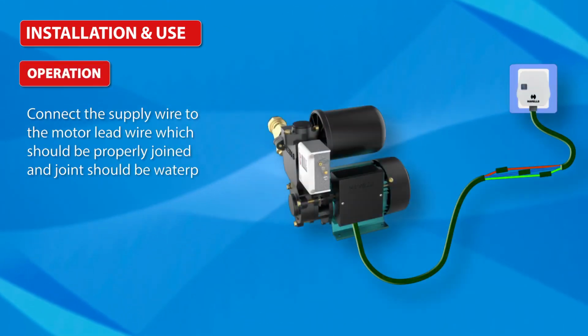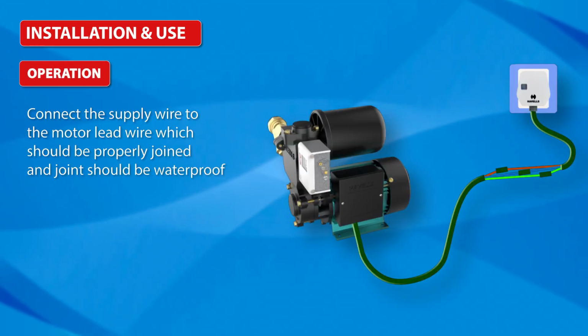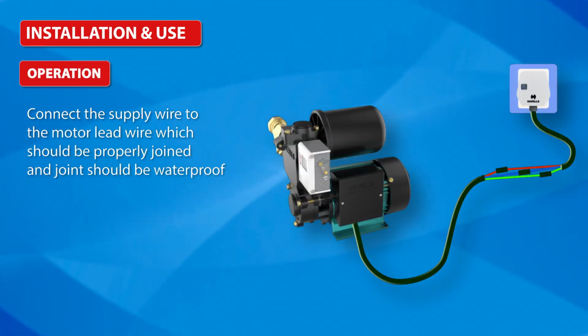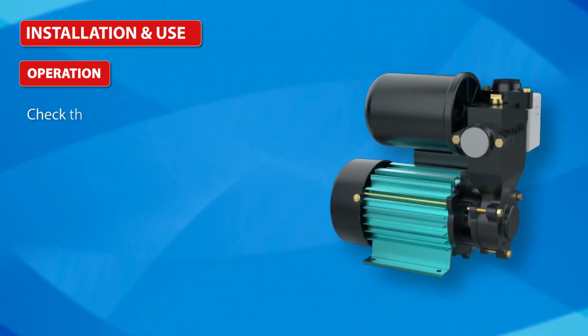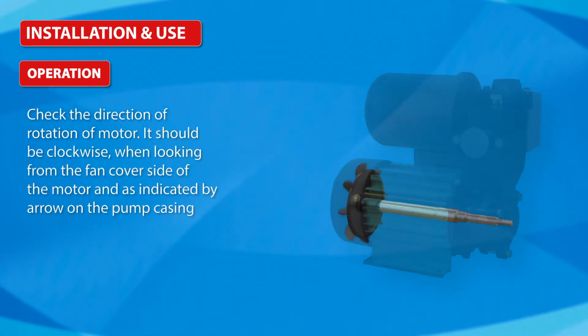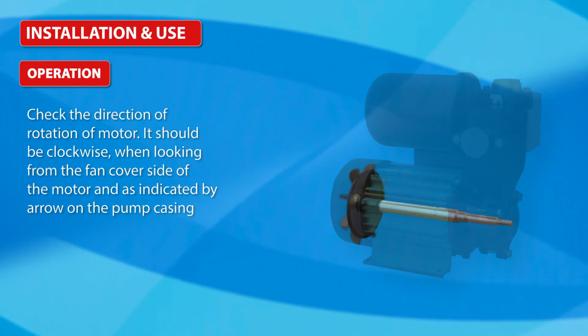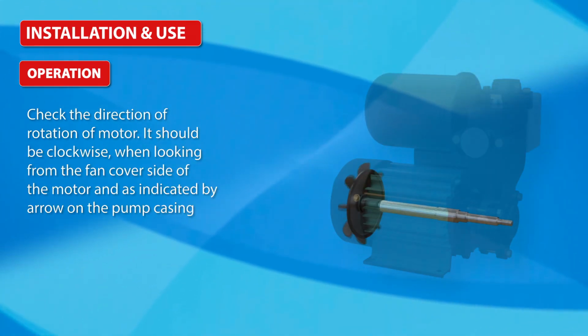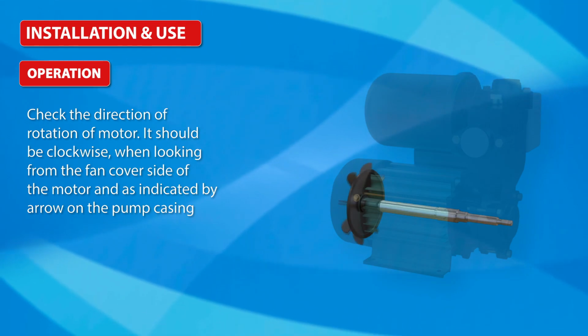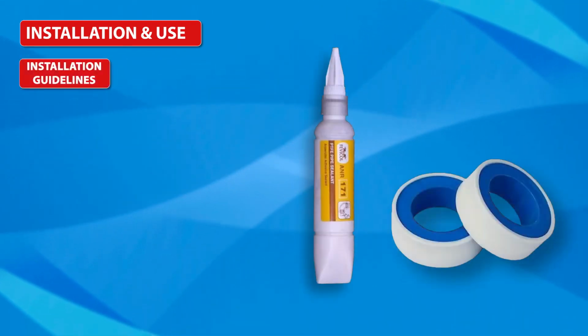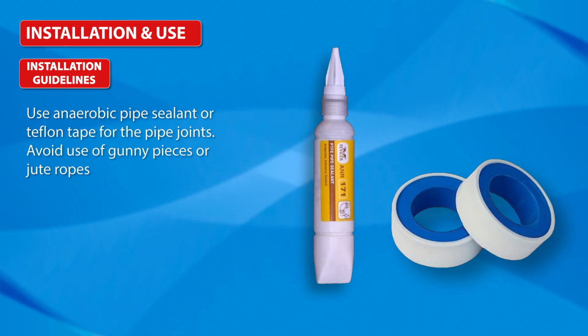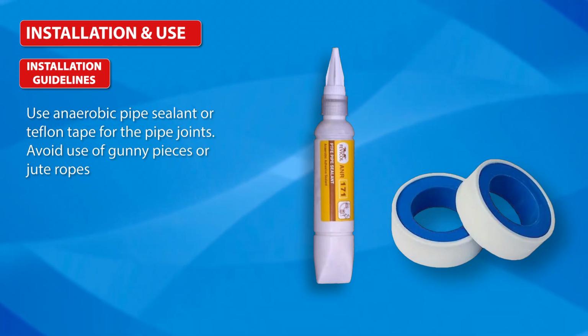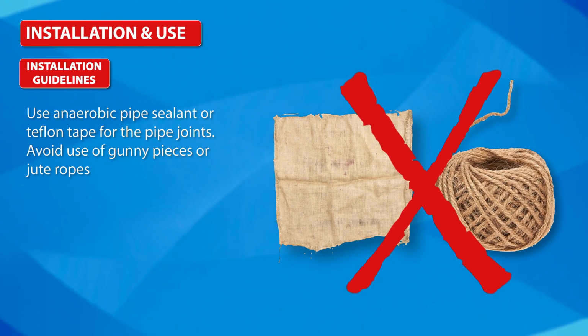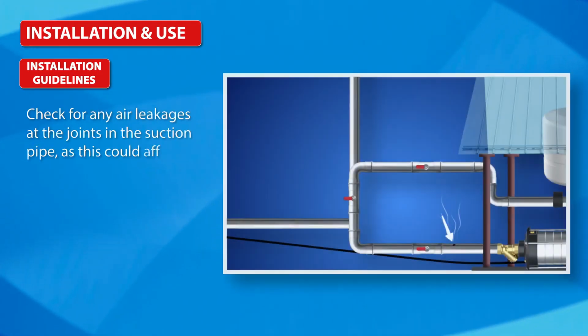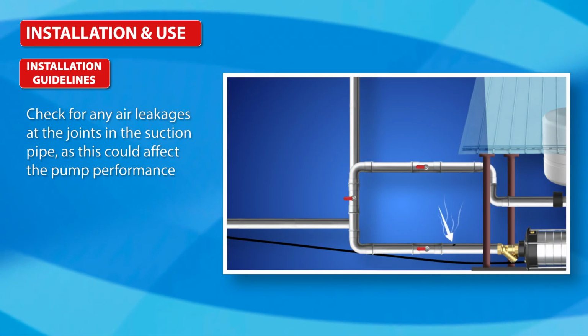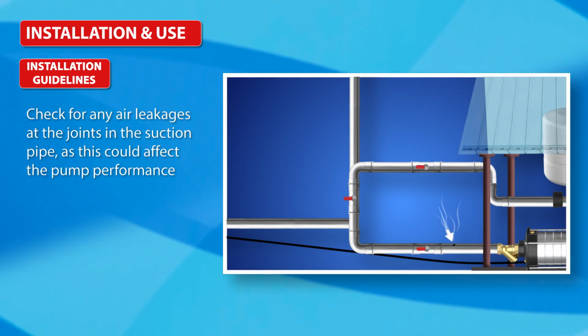Operation: connect the supply wire to the motor lead wire, which should be properly joined, and the joint should be waterproof. Check the direction of rotation of the motor. It should be clockwise when looking from the fan cover side of the motor and as indicated by the arrow on the pump casing. Installation guidelines: use anaerobic pipe sealant or Teflon tape for the pipe joints. Avoid use of gunny pieces or jute ropes. Check for any air leakages at the joints in the suction pipe, as this could affect pump performance.